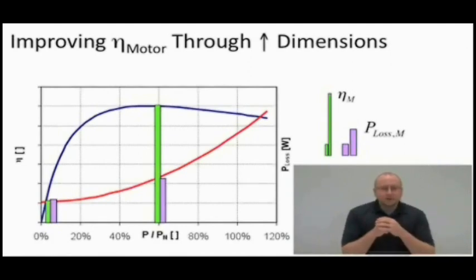The same is true for an asynchronous motor. If we look at this blue curve, the dark blue curve on the top, that shows us how the efficiency changes with loading. At 100% load, I have a certain efficiency, and then you see the curve kind of change a little bit. Actually, it really starts diving down when the motor is severely underloaded, and that's one of the things we were talking about earlier with an inverter. An underloaded motor is less efficient than a properly loaded motor. So what we can do is we can take, let's say a motor is rated for 5 horsepower. That would be 100% load, our rating. It has an efficiency of, let's look at this curve, say 85% is a good number for a regular standard efficiency motor of that size.